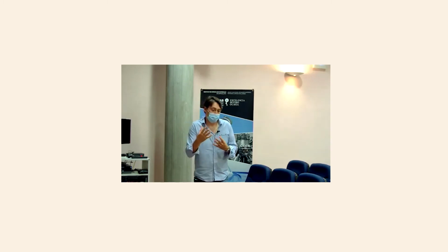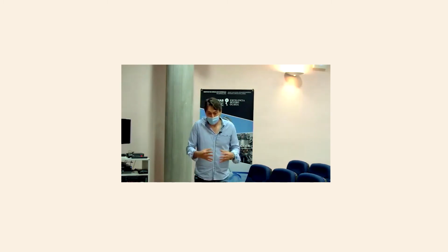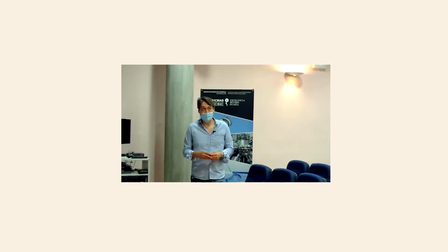What we recommend is to put your CO2 measurement at the level where people are breathing, because this is the important one. And not very close to people, not next to someone who is breathing on the meter. As you mentioned as well, the distribution of CO2 is not the same as the distribution of these aerosols, that's for sure. Because aerosols tend to decay, I can imagine that at some point you have more density at the lower levels, close to the floor, while CO2 doesn't have this behavior. So this is an ongoing experiment that we have been performing now from this Mesura group.